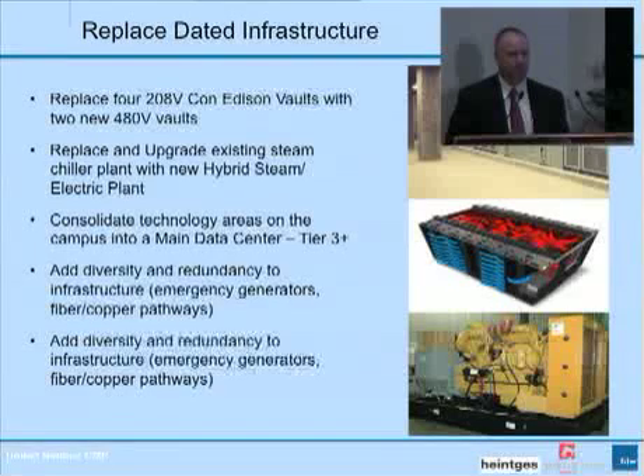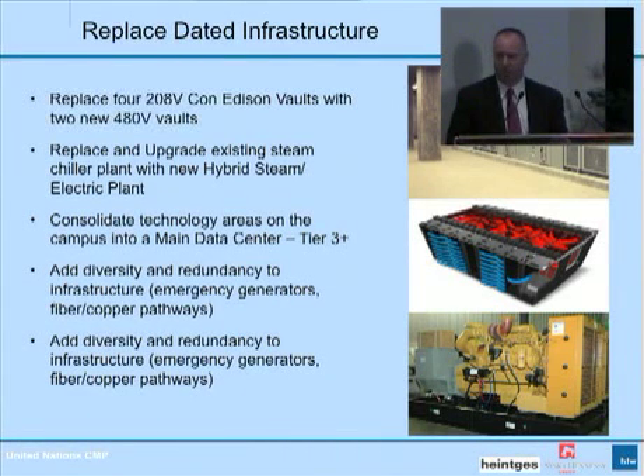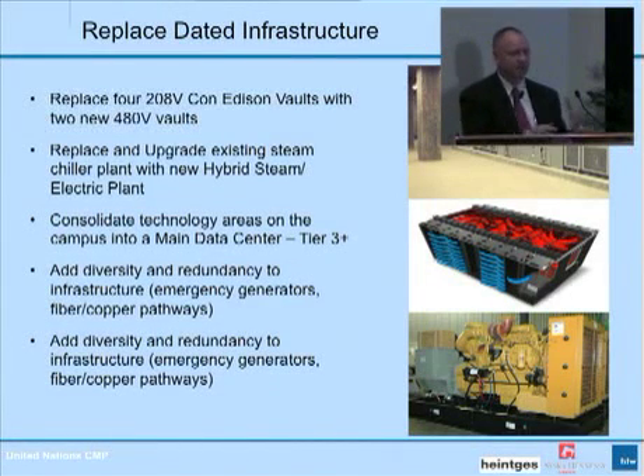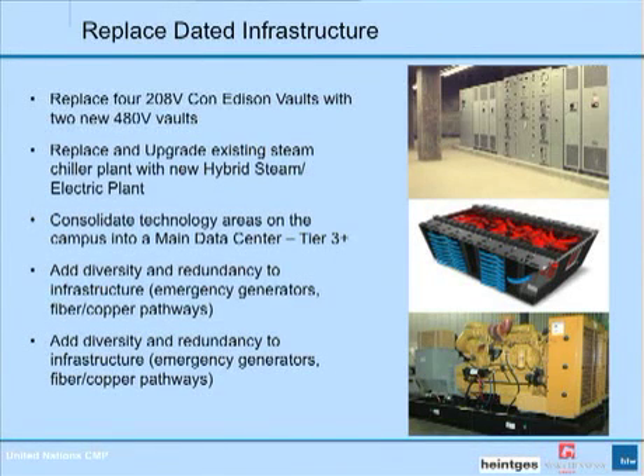Throughout the 50 years, different program units within the UN would build their own tiny data center to serve their program, or sometimes hide little data centers below their desk. We're bringing all these mini data centers into a tier 3 data center with a higher level of reliability and redundancy. Michael had shown earlier a picture of one of the high-density modules. And for anyone familiar with high-density data center design, these racks are designed to handle up to 20 kW per rack. That drives the space efficiency very high, and also drives the overall equipment efficiency to a high level.